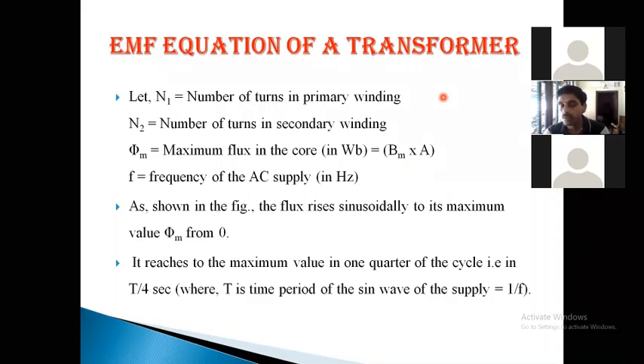And one important question is, if the frequency is changed, what happens to the transformer? Definitely, if the frequency changes, losses will change and the size of the transformer increases. Because if F increases, reactance XL equal to 2 pi F L, the reactance of the winding increases, therefore the size of the transformer increases. So the frequency generally is constant. If it varies, what happens? That is the general question, a reasoning question. So F is the frequency of the supply.